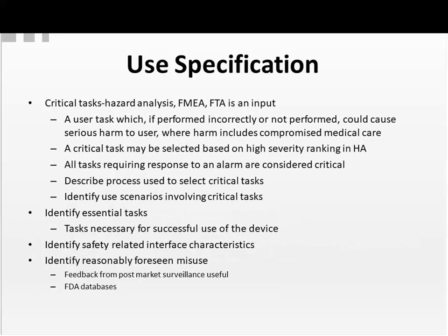We identify the critical tasks. And this can come from a hazard analysis, an FMEA, FTA, other types of risk analysis. A critical task is a user task which, if performed incorrectly or not performed, could cause serious harm to the user, where harm includes compromised medical care.